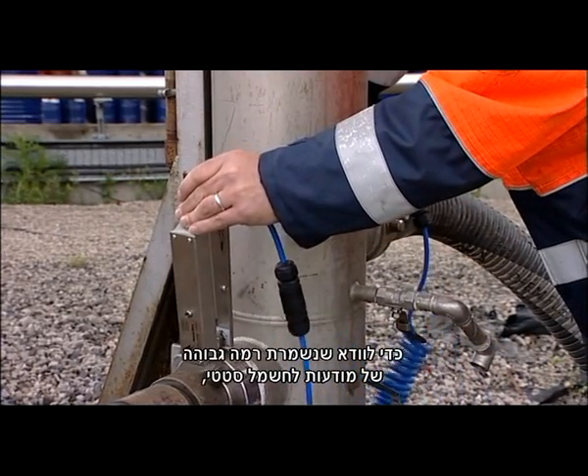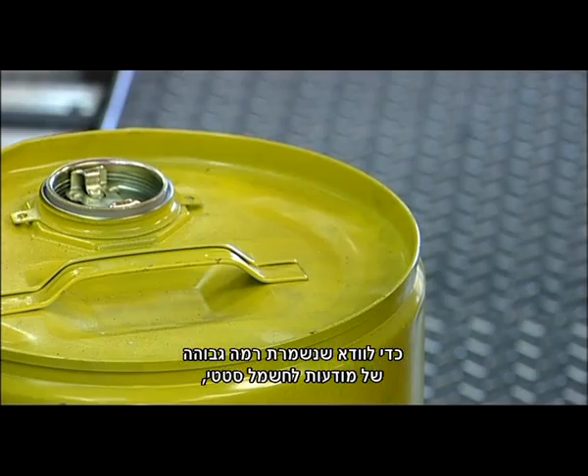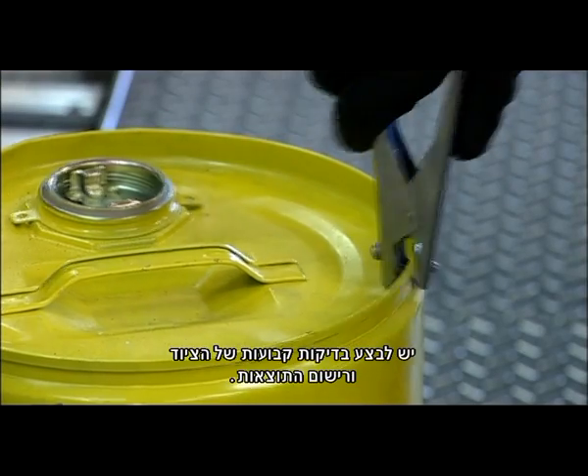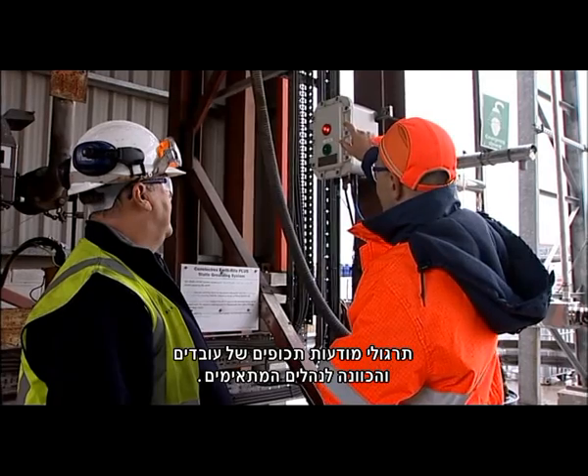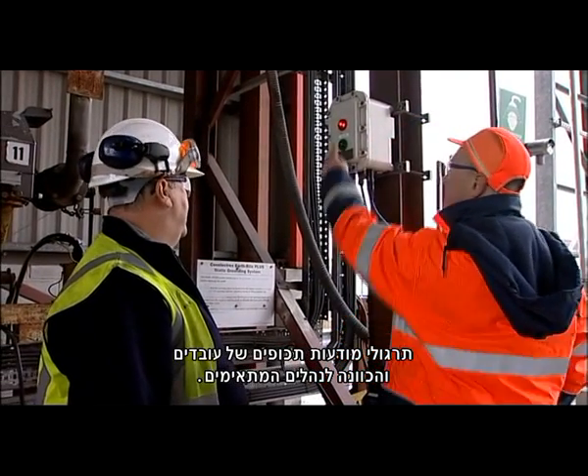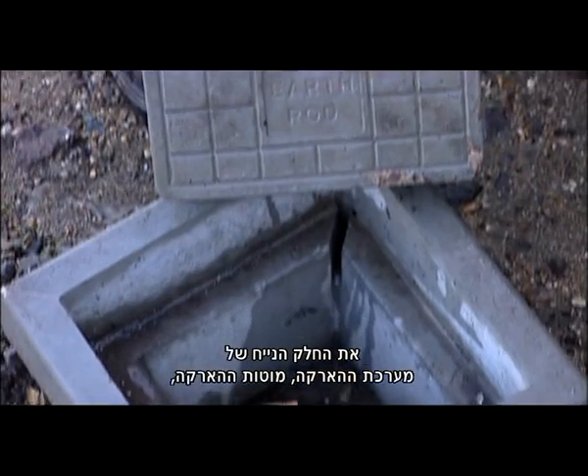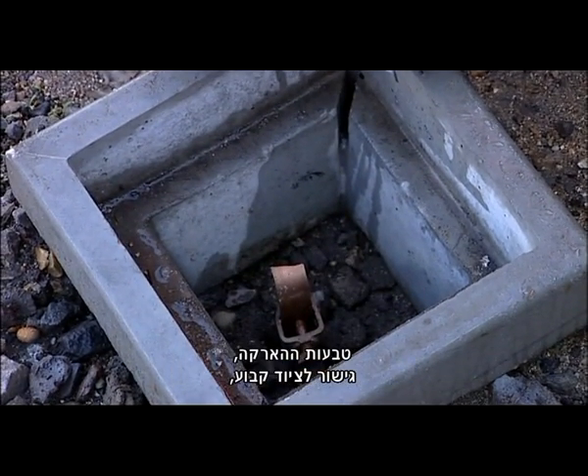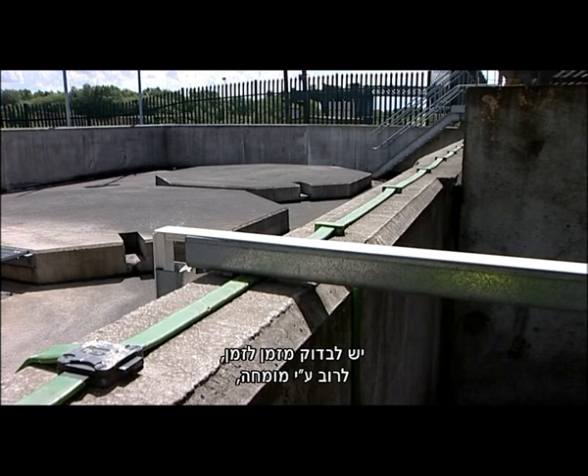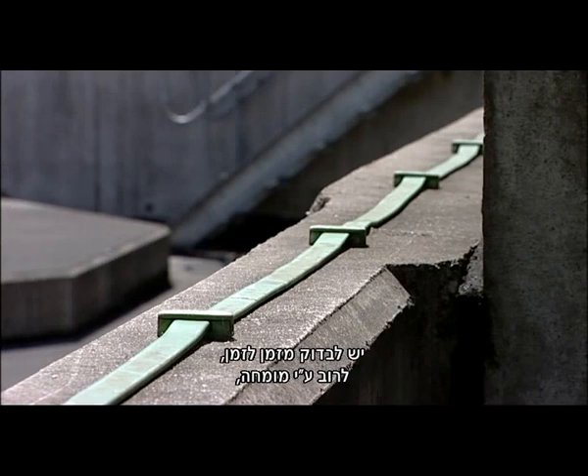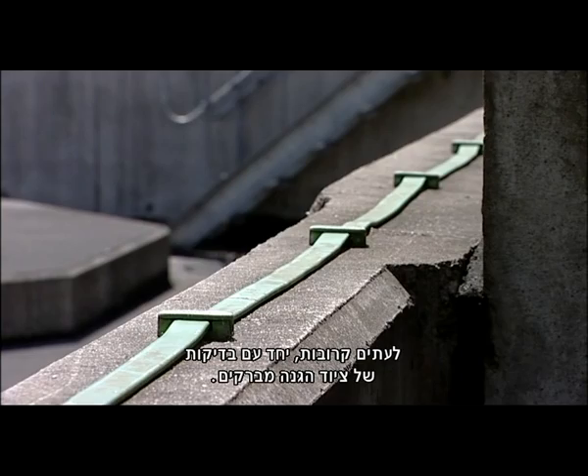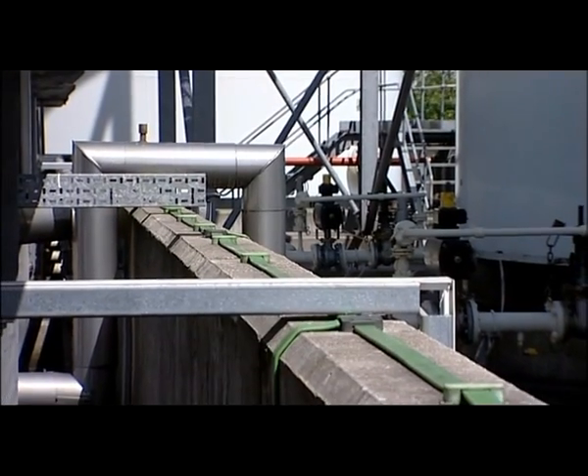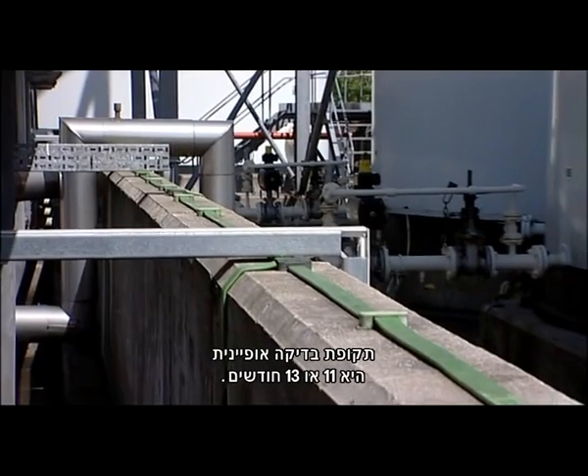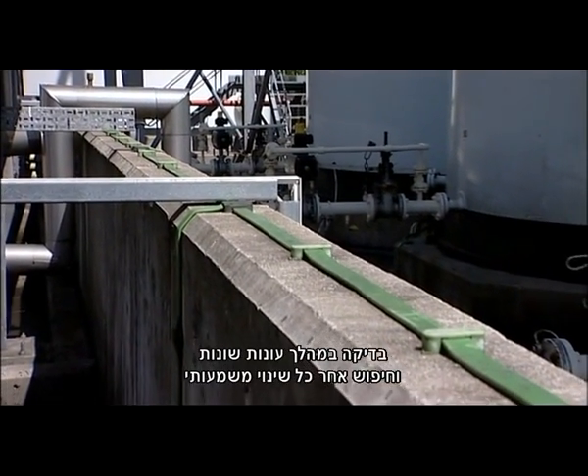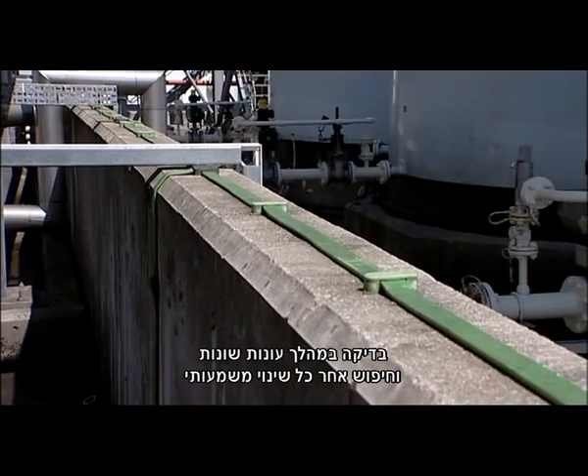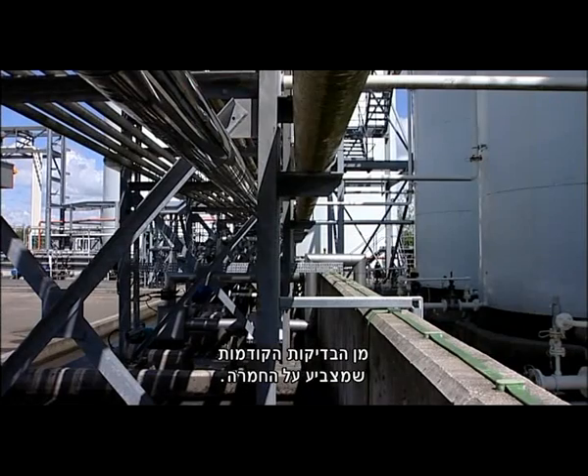To ensure a high level of static electricity awareness is maintained, there should be regular testing of equipment with results logged, frequent awareness training of operators, and reference to the appropriate standards. The fixed part of the earthing system, the earthing rods, the earthing loop, and bonding on fixed equipment should be tested periodically, usually by a specialist, often in conjunction with tests on lightning protection equipment. A typical test period would be 11 or 13 months, testing during different seasons, and would look for any significant variation from previous tests, indicating deterioration.